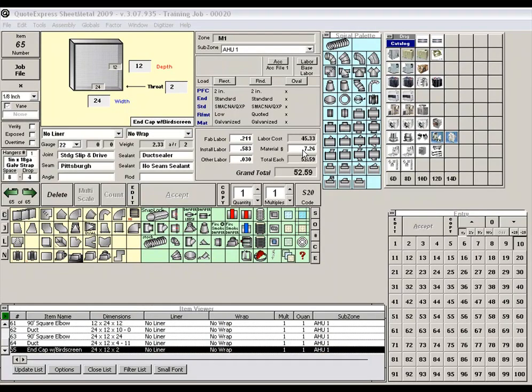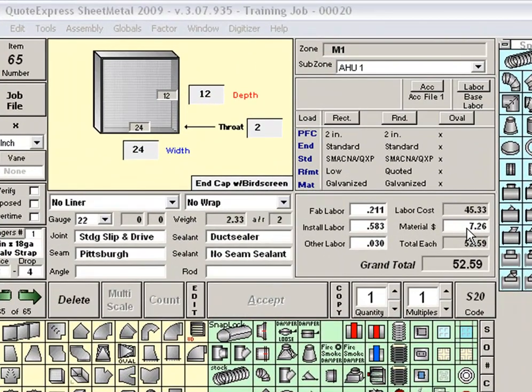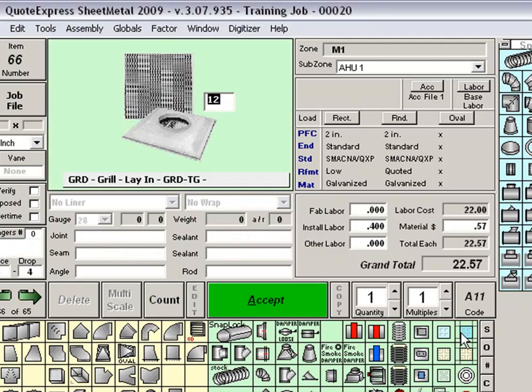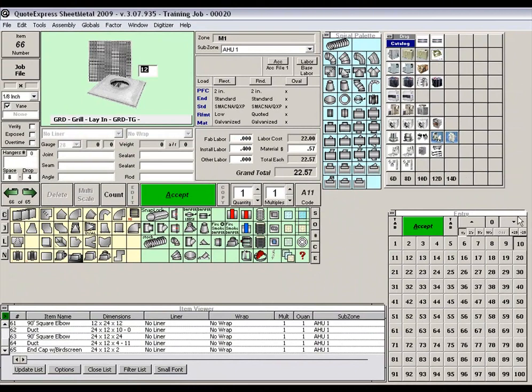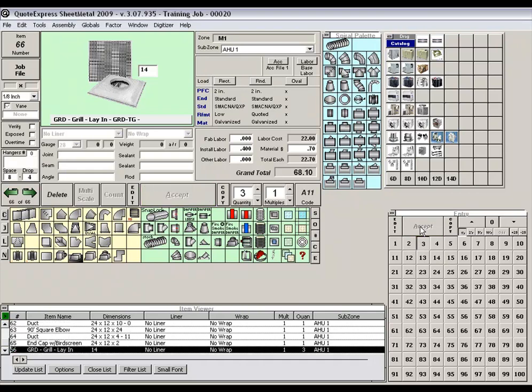The last part of the takeoff are 3 lay-in diffusers for the return air grills, open air plenum style. Select the lay-in diffuser, select the diameter that we wish to use, and put in 3 as the quantity, and then accept. And this would complete the takeoff.